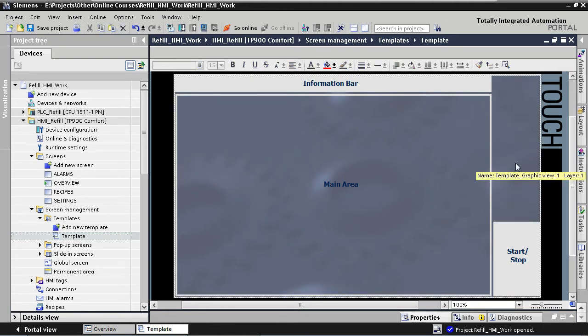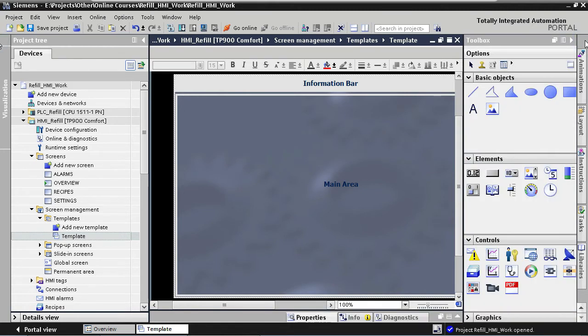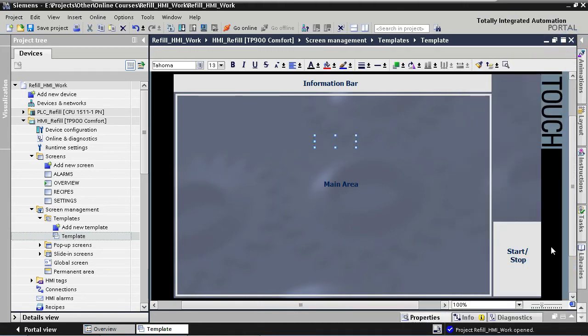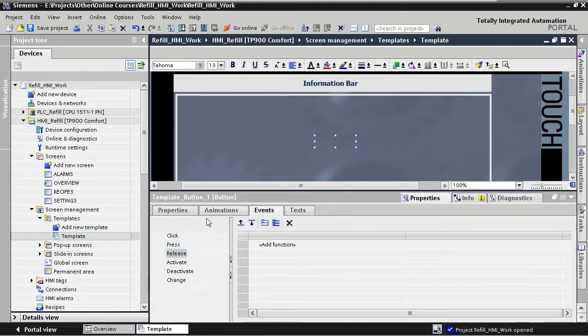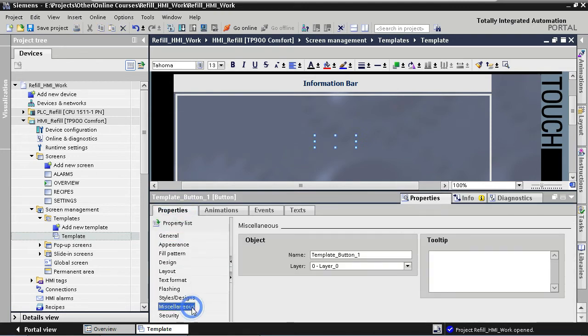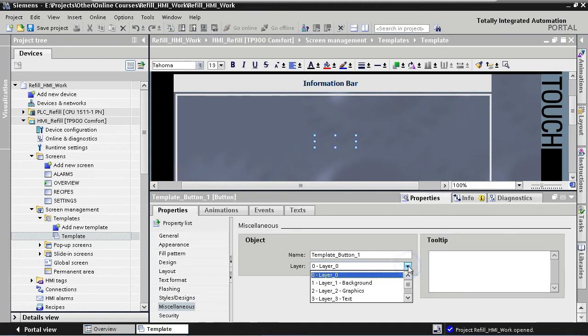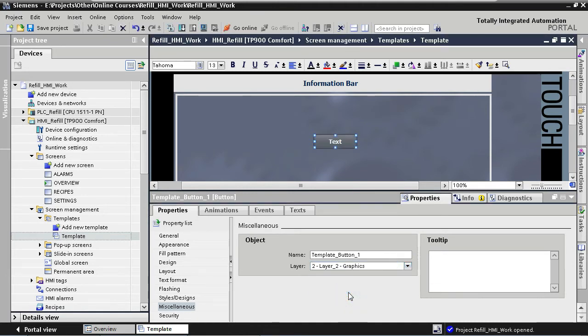The first button we're going to add is our process overview button, which will allow the user to jump to the process overview screen. To add a button to the template, we open the toolbox on the right and drag and drop the button element to the template. We assign Layer 2, which is our graphics layer, to the button. This is the default button in TIA Portal — it doesn't look too bad, but I think we can do much better. Let's implement custom graphics instead of the default color transition and text.